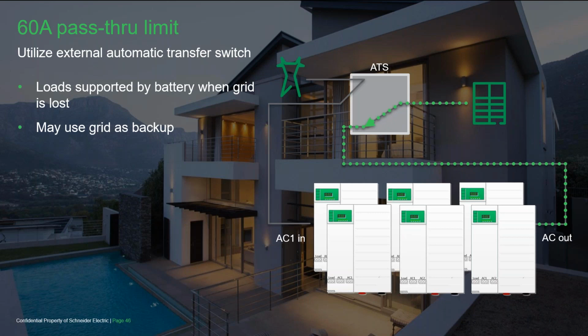If you can use an automatic transfer switch that has a dry relay contact to force transfer to the emergency side when the normal input is energized, in other words, using the grid on the emergency side, you can use the XW Pro aux port and an automotive relay to connect to the grid only when the batteries get low. This is a great solution for self-consumption.